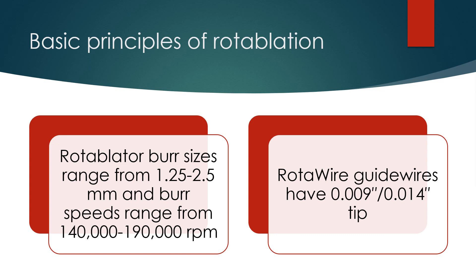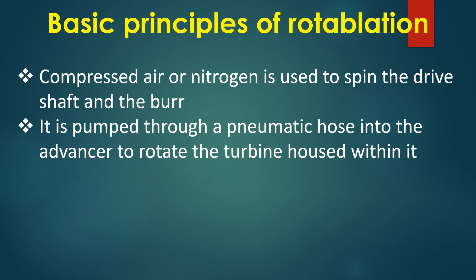Rotablator bur sizes range from 1.25 to 2.5 mm and bur speeds range from 140,000 to 190,000 rpm. Rotawire guidewires have 0.009 inch and 0.014 inch tips. Compressed air or nitrogen is used to spin the drive shaft and the bur, pumped through a pneumatic hose into the advancer to rotate the turbine housed within it.